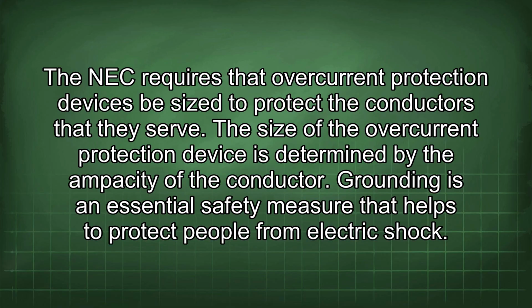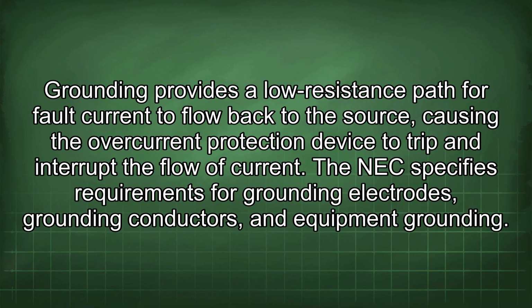Grounding is an essential safety measure that helps to protect people from electric shock. Grounding provides a low resistance path for fault current to flow back to the source, causing the overcurrent protection device to trip and interrupt the flow of current. The NEC specifies requirements for grounding electrodes, grounding conductors, and equipment grounding.